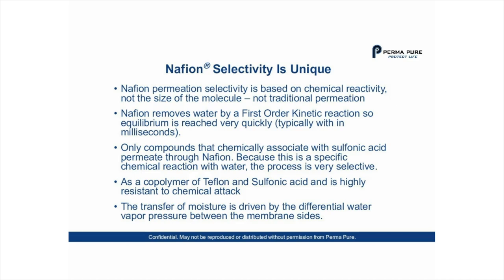As a copolymer of Teflon and sulfonic acid, Nafion is highly resistant to chemical attack. The transfer of moisture is driven by the differential water vapor pressure between the membrane sides — that applies to gas-to-gas transfer. For water-to-gas transfer, the water simply permeates and moves through the membrane as a liquid.